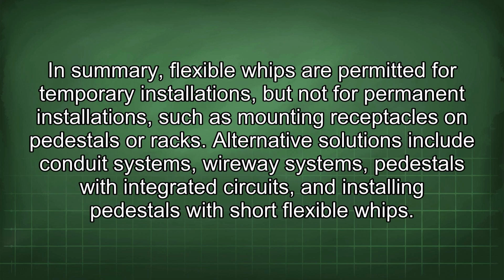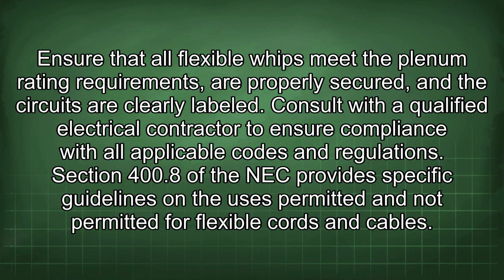In summary, flexible whips are permitted for temporary installations but not for permanent installations, such as mounting receptacles on pedestals or racks. Alternative solutions include conduit systems, wireway systems, pedestals with integrated circuits, and installing pedestals with short flexible whips. Ensure that all flexible whips meet the plenum rating requirements, are properly secured, and the circuits are clearly labeled.